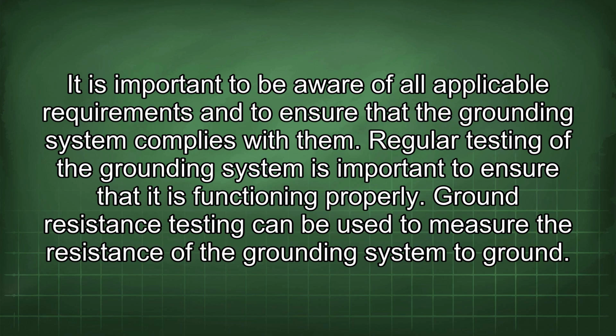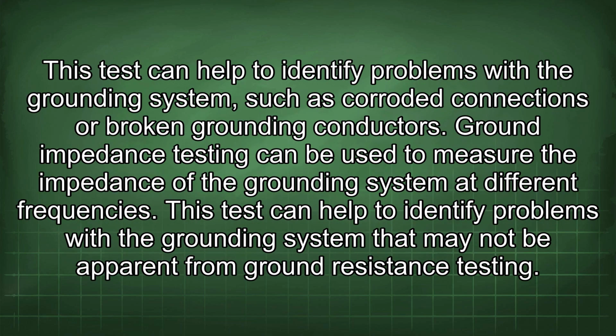Ground resistance testing can be used to measure the resistance of the grounding system to ground. This test can help to identify problems with the grounding system, such as corroded connections or broken grounding conductors. Ground impedance testing can be used to measure the impedance of the grounding system at different frequencies. This test can help to identify problems with the grounding system that may not be apparent from ground resistance testing.